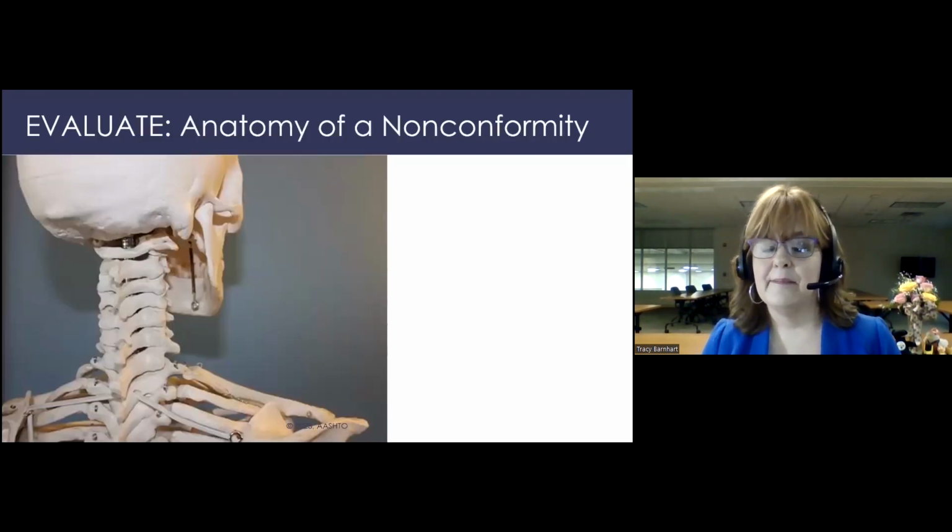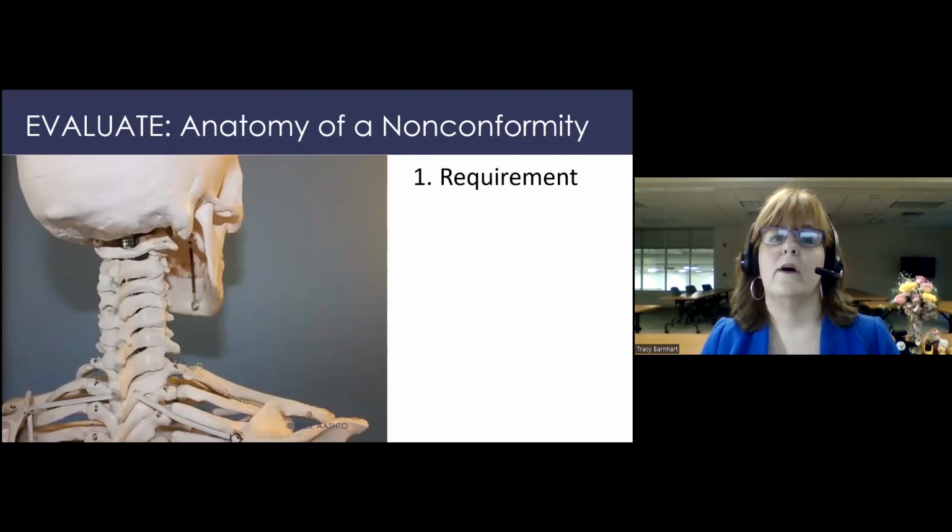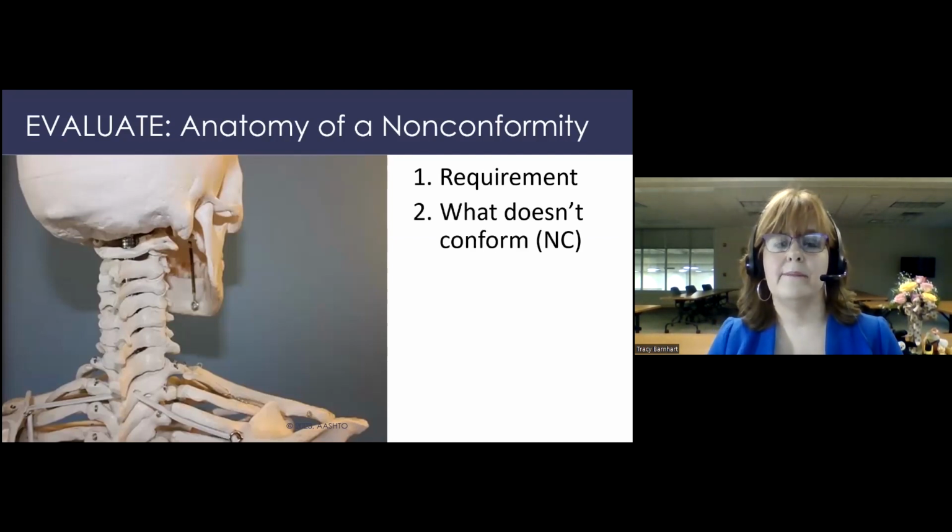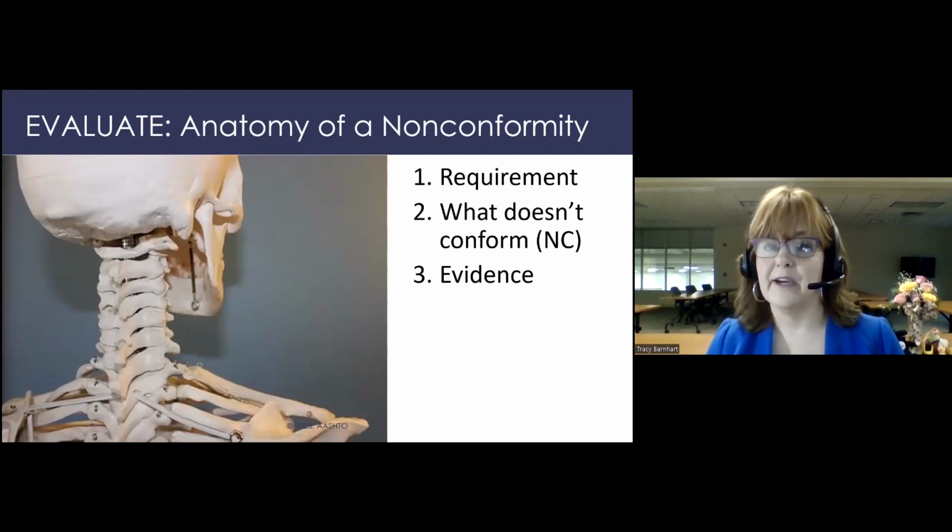All right, anatomy of a nonconformity. Nonconformities really have to have 3 parts. What is the requirement? I talked about that, linking everything to a requirement. What doesn't conform? What is the nonconformity, essentially? And what is your evidence to support the nonconformity?